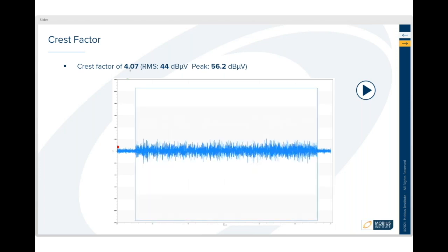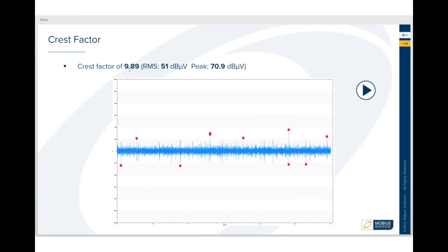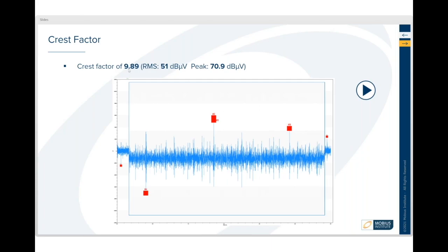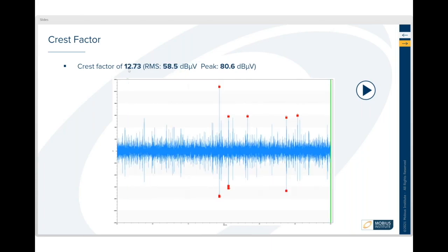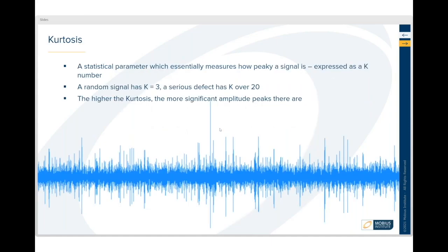But as there are more spikes, you can see the RMS—if you just keep an eye on the peak and the RMS—you can see how the crest factor, which is a ratio, is changing. You can see there are more spikes there, and then the crest factor is higher again as there are more spikes. So it is a good measure to use.